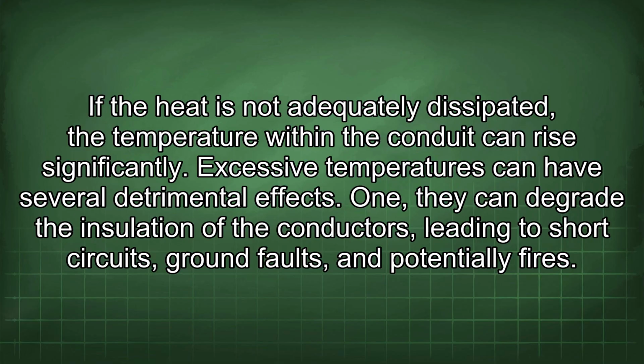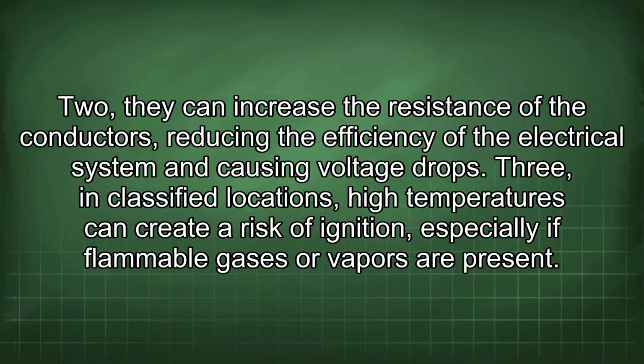Excessive temperatures can have several detrimental effects. 1. They can degrade the insulation of the conductors, leading to short circuits, ground faults, and potentially fires. 2. They can increase the resistance of the conductors, reducing the efficiency of the electrical system and causing voltage drops. 3. In classified locations, high temperatures can create a risk of ignition, especially if flammable gases or vapors are present.